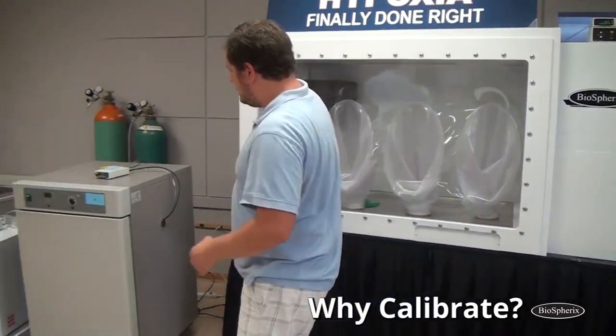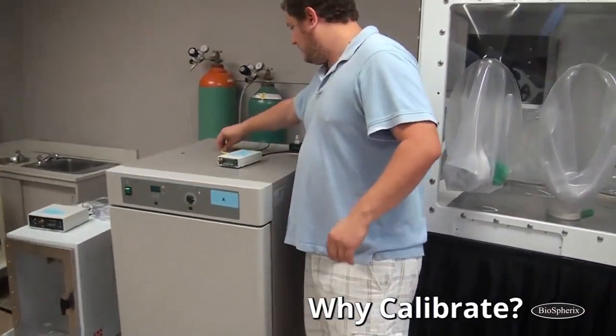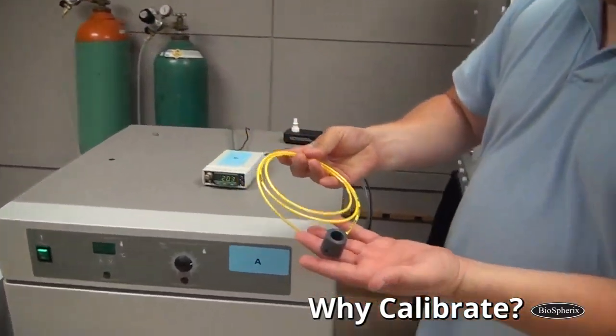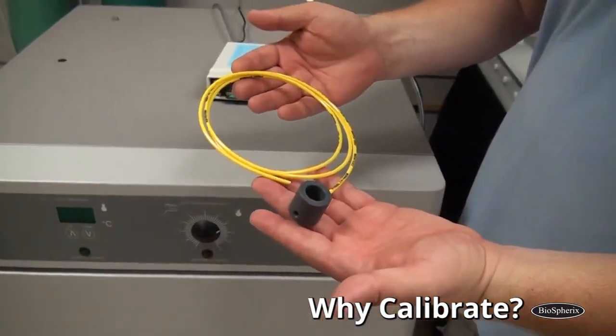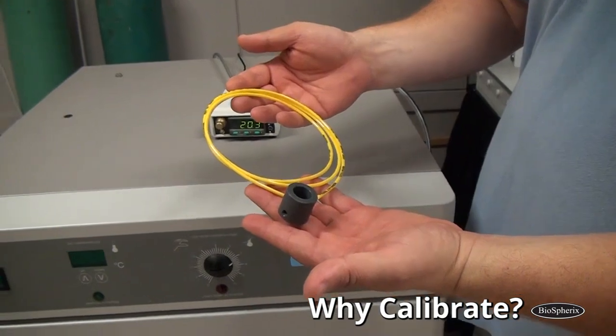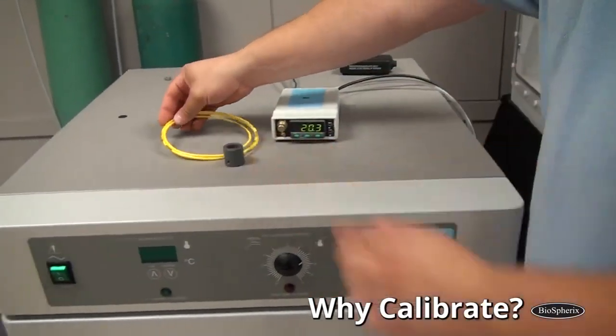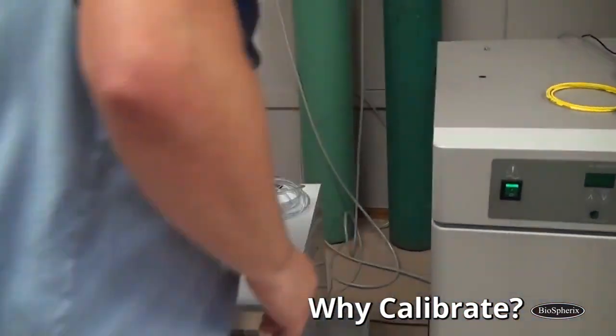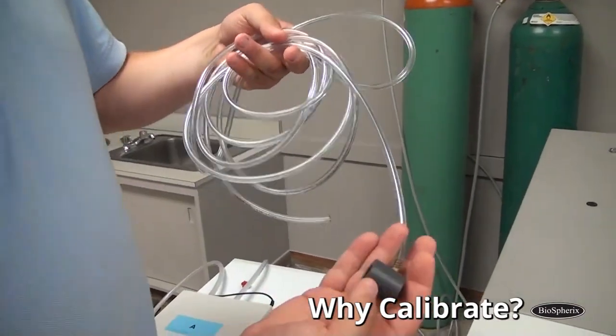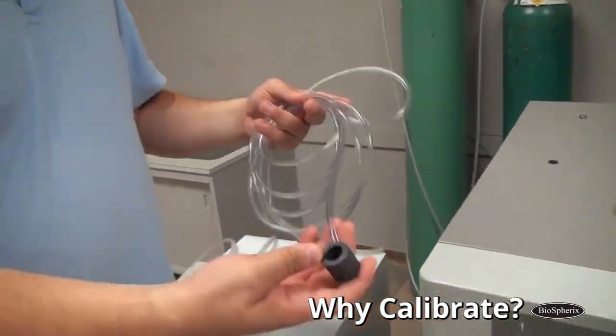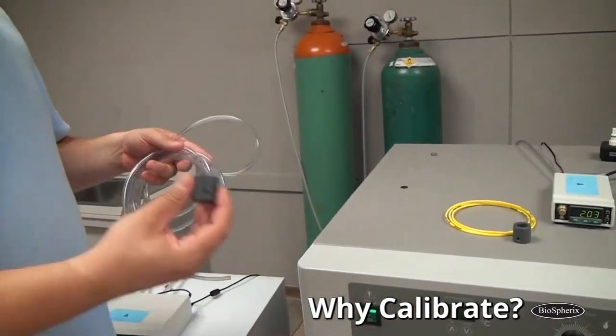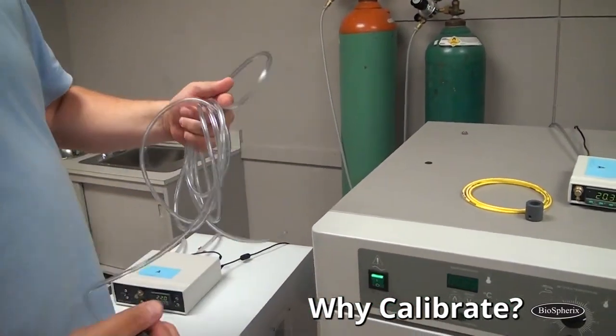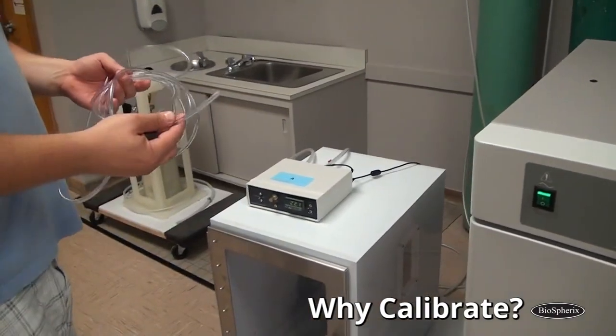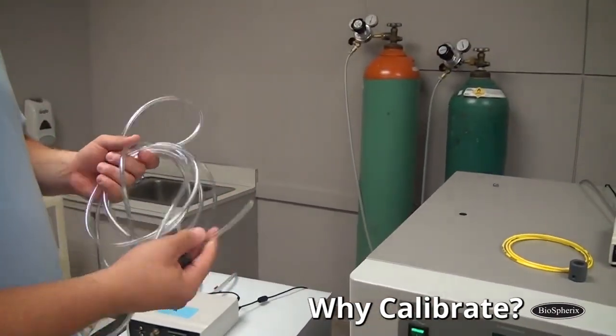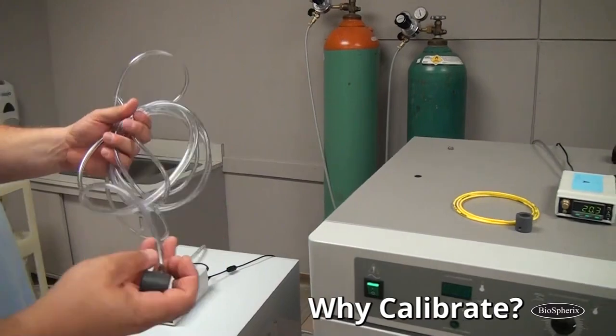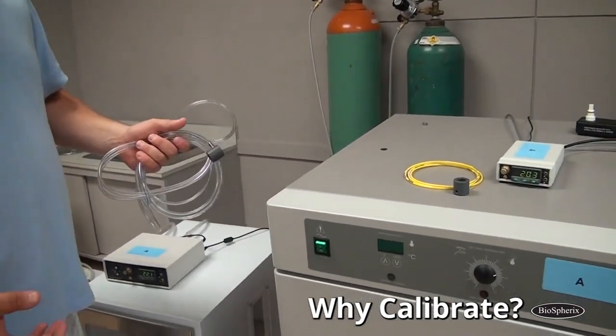The key piece when you go to calibrate is going to be your calibration chamber. It'll look like this if you have a model P110, or it will look like this if you have a model P360. They're exactly the same cup, work exactly the same way. The only difference is because the model P360 is a little larger controller, it has a little larger tubing to it. You're going to find this in the bag kit that comes with the controller.